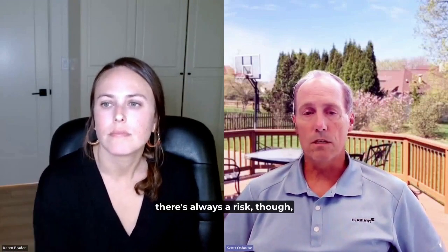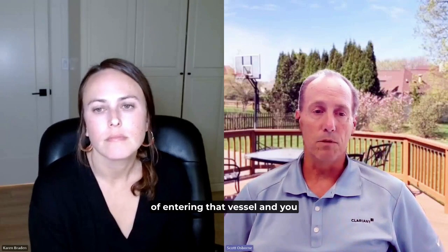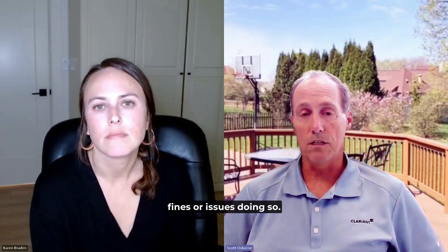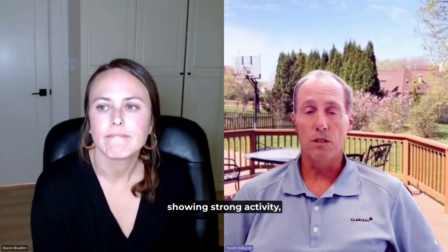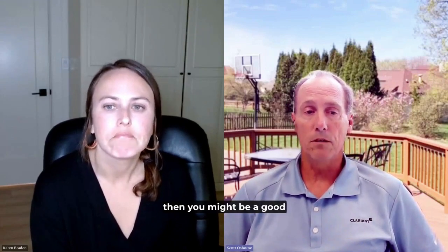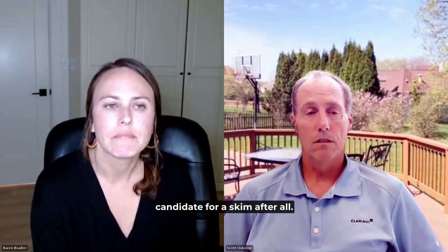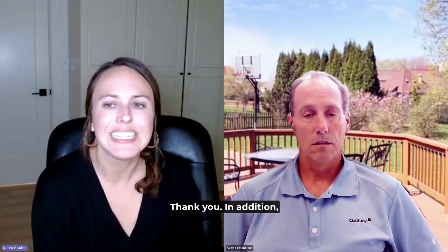Now, there's always a risk, though, of entering that vessel and you potentially create additional fines or issues doing so. And so, for instance, if your catalyst is 6 years old, a skim really might not be a good idea. But if it's 1 year old and showing strong activity, then you might be a good candidate for a skim after all.